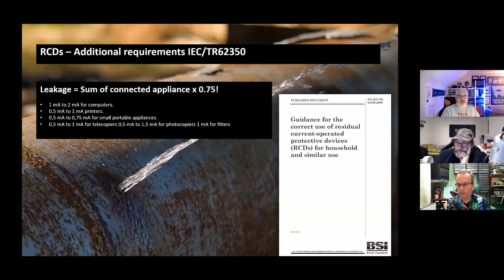But we've since discovered that Schneider have recently produced a good guide to RCDs with lots of values. But John, we know there are even more. They're hidden behind a £24,000 paywall from the Broken Standards Institute. Yeah, the problem with that is that there's a whole set of standards, about 108 of them or something, and each one deals with a very specific type of appliance. So there might be one for coffee makers and one for washing machines, and there's a line in each one that tells you what the leakage for that particular type of appliance is. So to get all of them, you'd have to literally spend that, 28,000 quid or whatever it was, get all the standards and look in each one, and on that single line, oh yes, that's 6 milliamps for such and such and 3 milliamps for this and all of that.